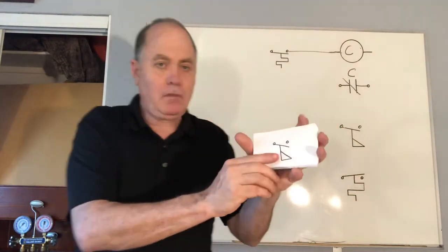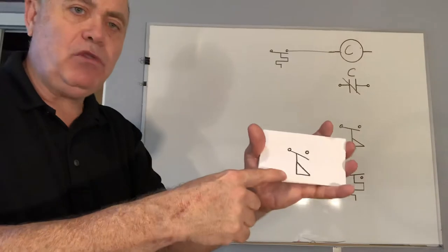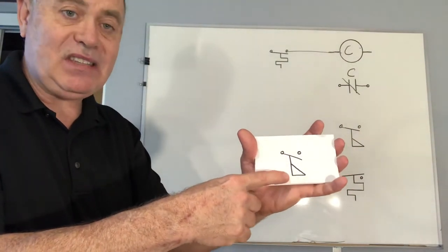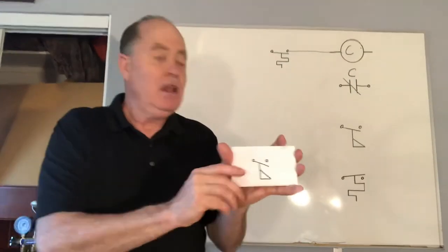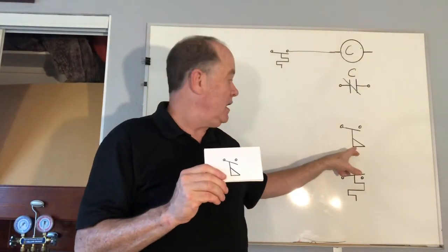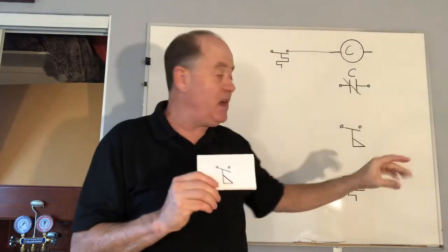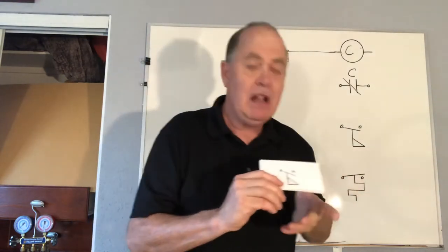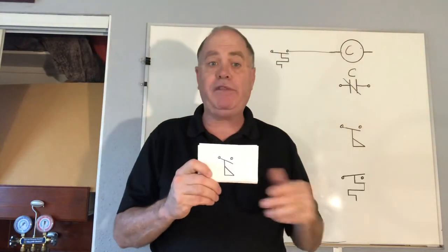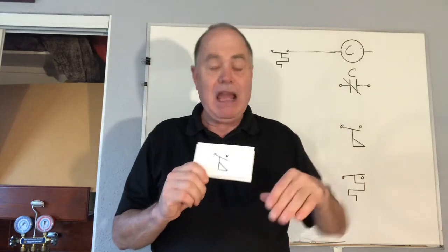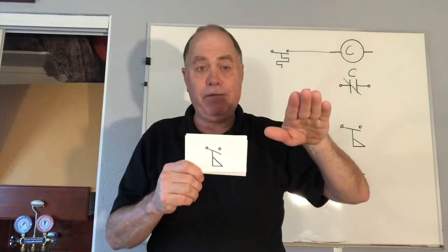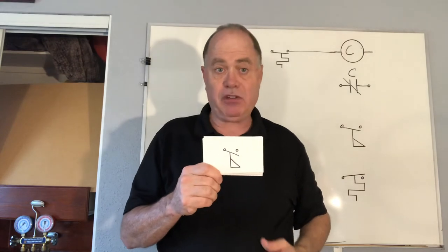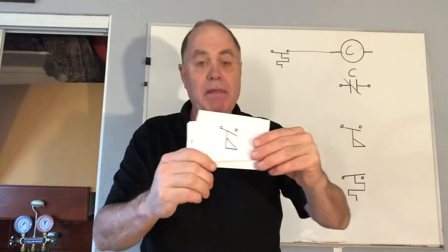The flow switch is also known as a paddle switch or sail switch because it makes with flow of fluid — either vapor or liquid. For air flow, a fan running lifts the sail up and it closes the contacts. With something like a chilled water pump, when the pump is energized a paddle switch confirms water flow, and then we're allowed to bring on the compressor to make chilled water. So a flow switch makes with flow, whether sail or paddle.